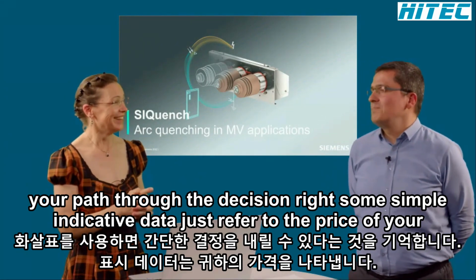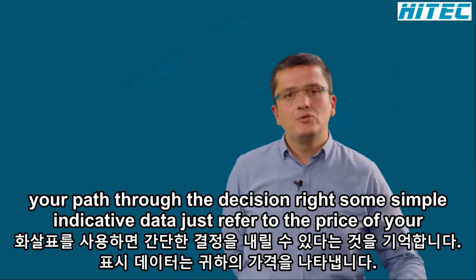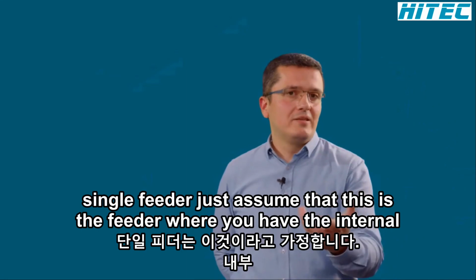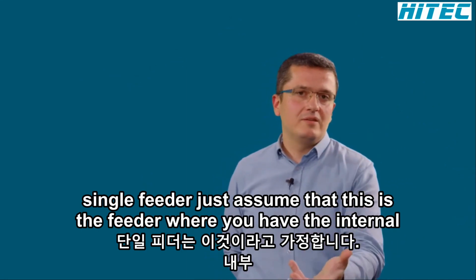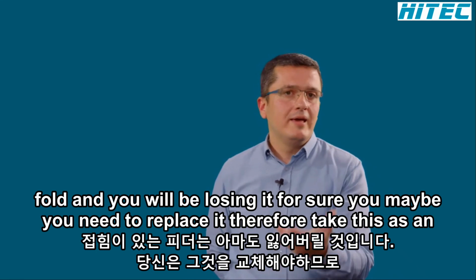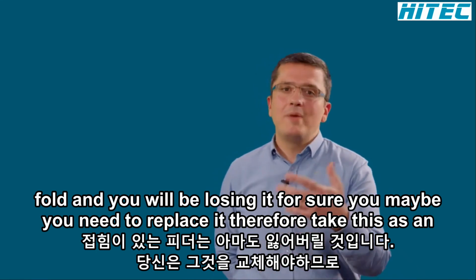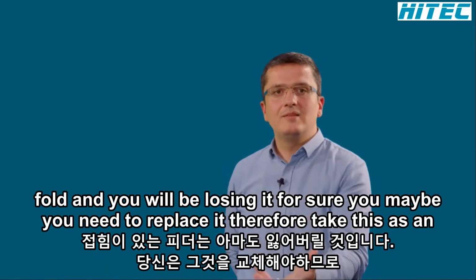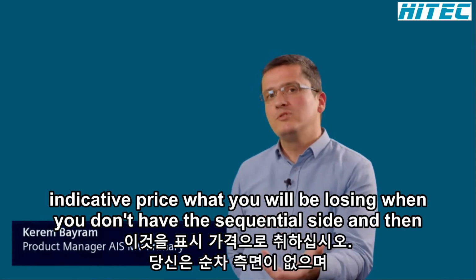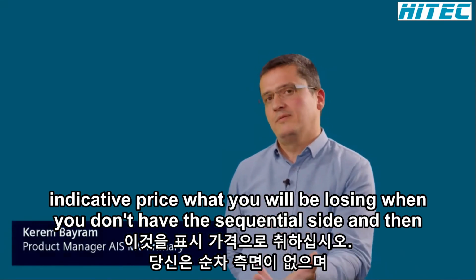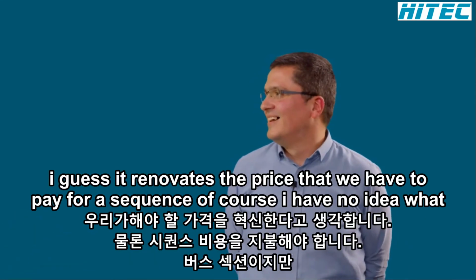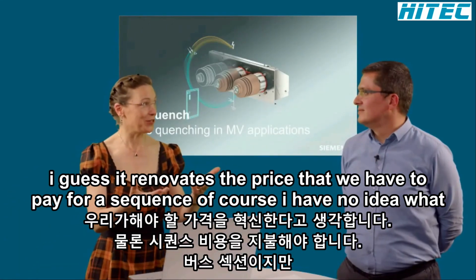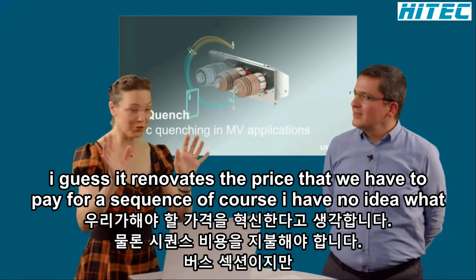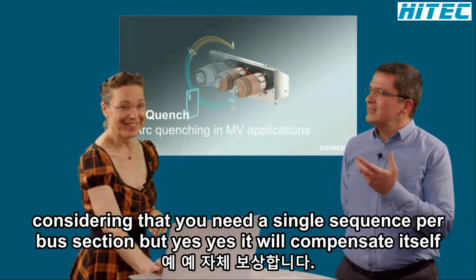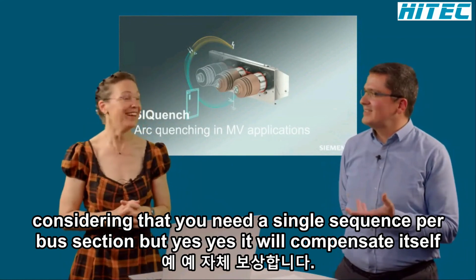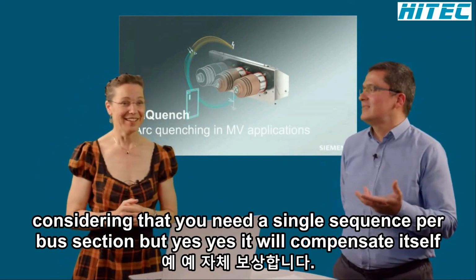Sure, as some simple indicative data, just refer to the price of your single feeder. Assume this is the feeder where you have the internal arc fault, and you will be losing it for sure, maybe needing to replace it. Take this as an indicative price of what you will be losing when you don't have SIQuench itself. And then I guess that relates to the price we have to pay for SIQuench. Considering that you need a single SIQuench per bus section, yes, it will compensate itself.